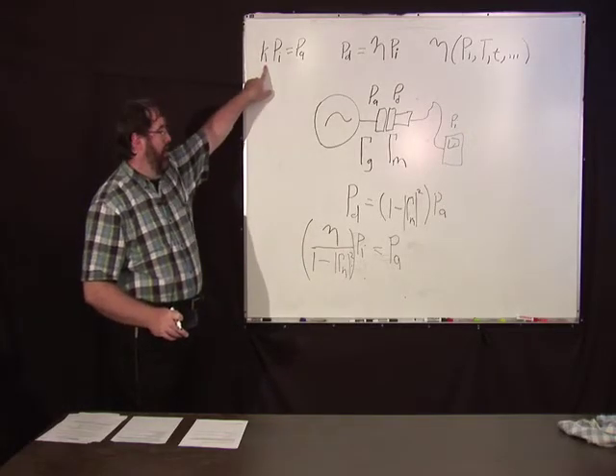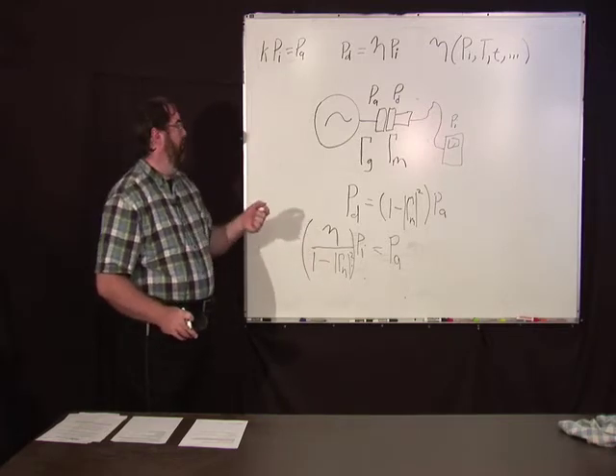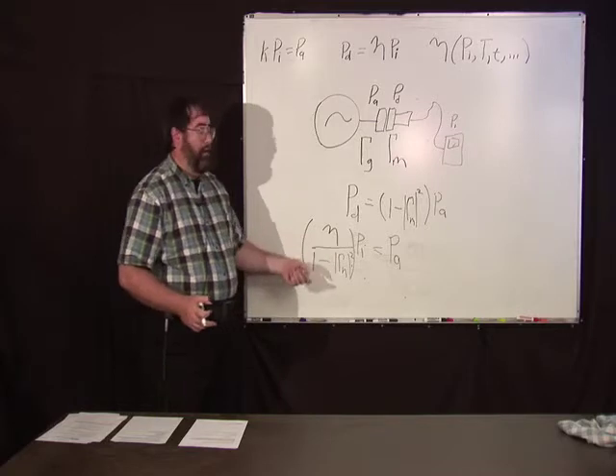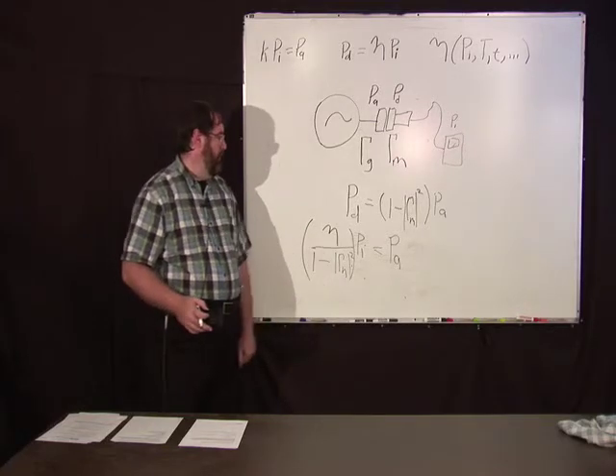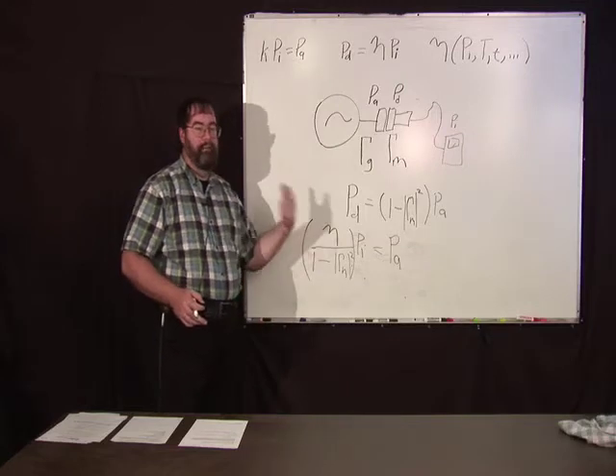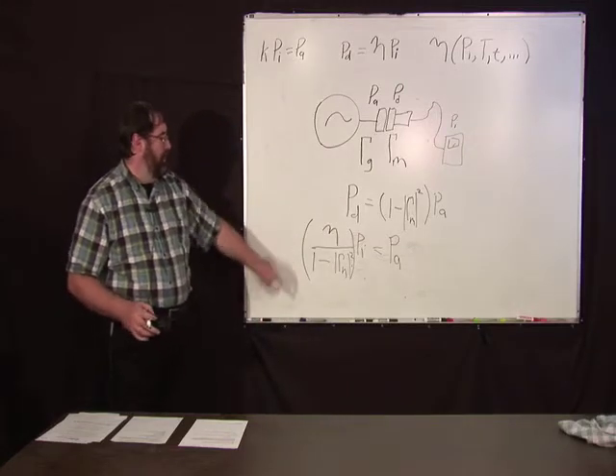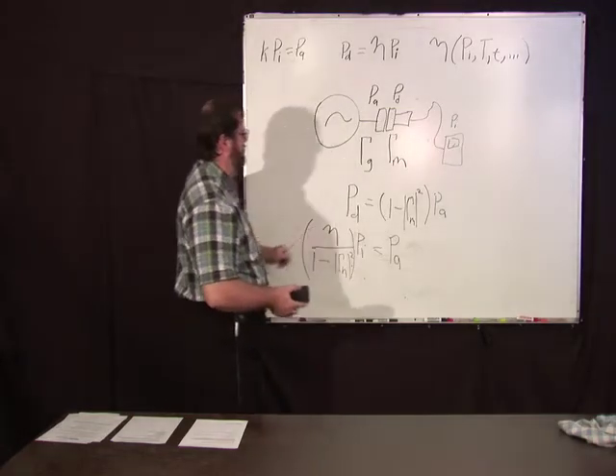This will give you the available power in terms of the indicated power. Often we just want to know this k, so the gamma is usually included when you do a power sensor. The cal factor is this one over this quantity, because you divide by the cal factor in the meter. But this doesn't tell the whole story.